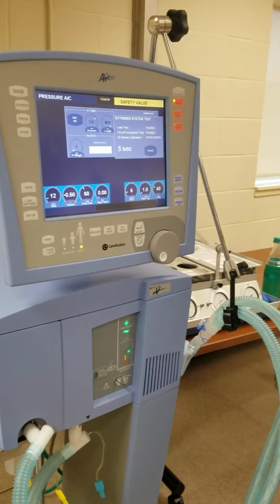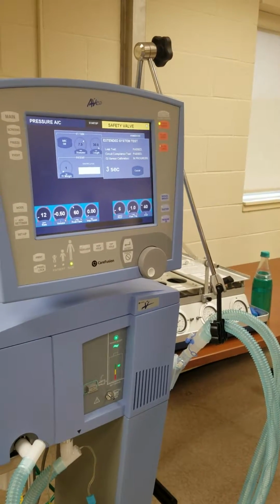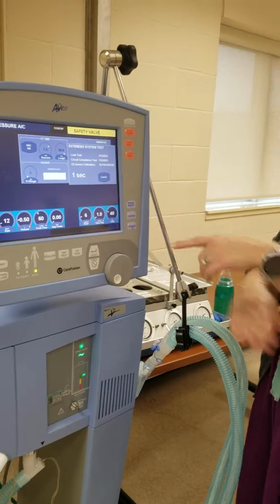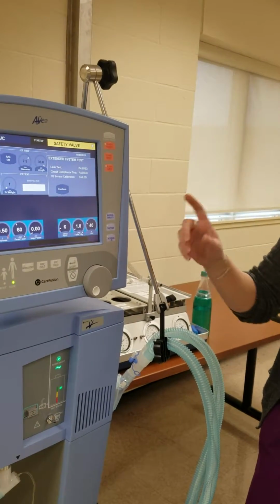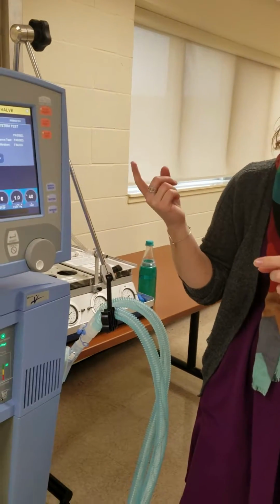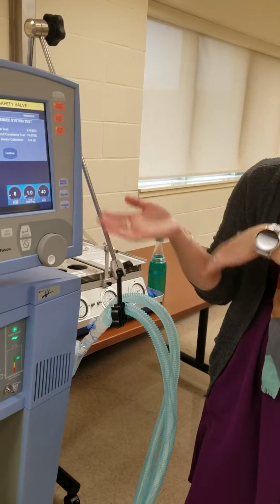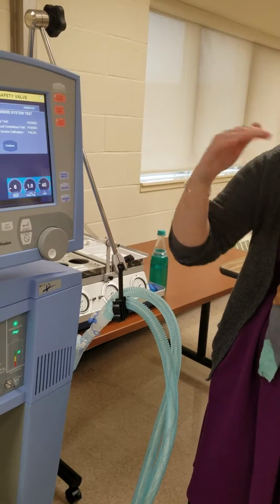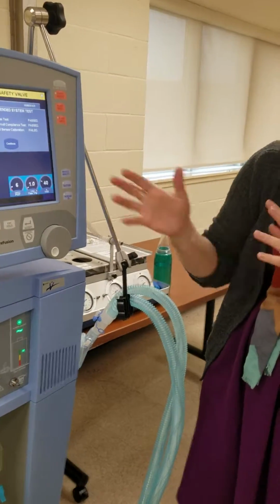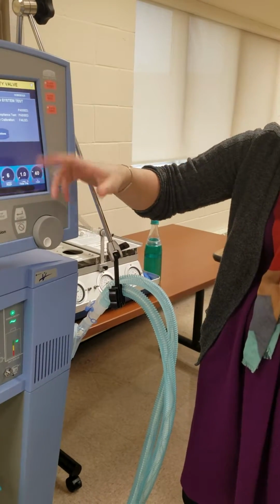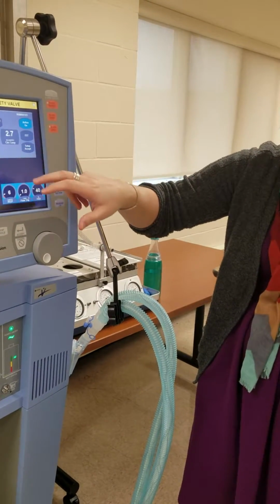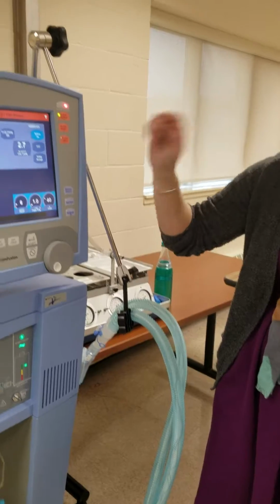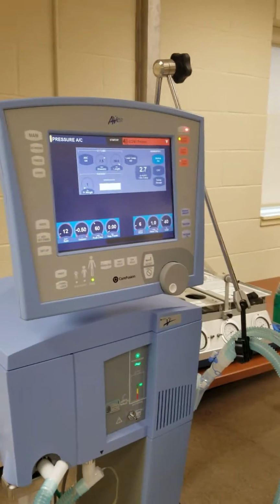And we wouldn't want to be hooked up to a patient right now because the ventilator's not feeling it. And during the O2 sensor calibration, what it does is internally it cranks the FiO2 up to 100, makes sure that it hits 100, it cranks it back down to 21. It's just zeroing and calibrating that oxygen sensor. So it failed. Again, it's probably just expired. Again, alarm silence. You'll see I keep hitting up here.